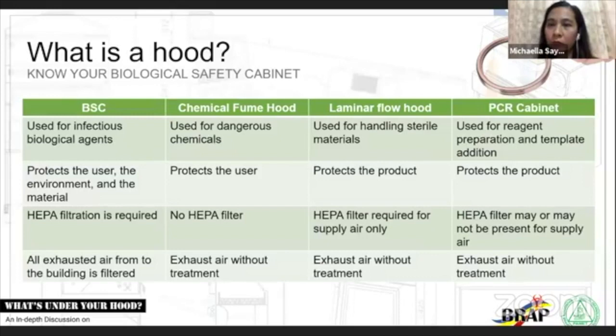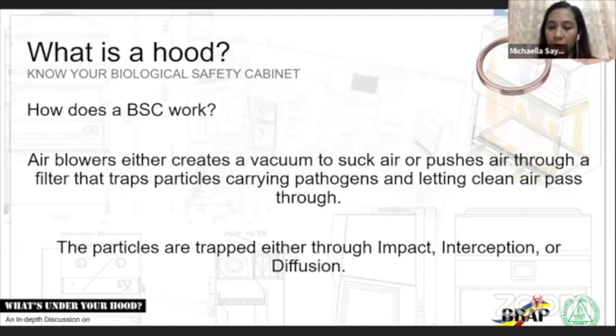Right, next. Now, how does a BSC work? Do you know how your BSC works? Okay. Basically, air blowers either create a vacuum to suck in air or push air through filters. Again, the filters may be HEPA filters or ULPA filters that trap particles carrying pathogens of a certain size, letting clean air pass through, which creates your quote-unquote air curtain that prevents the pathogens from escaping your cabinet, and clean air within the cabinet to prevent cross-contamination.